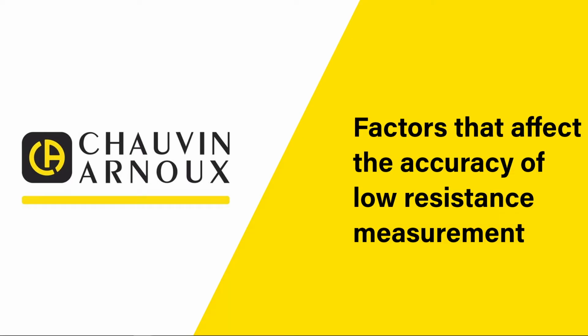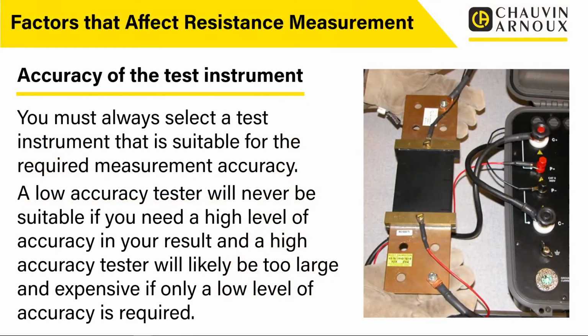So now we're going to take a look at the factors that affect the accuracy of low resistance measurement. The first factor we're going to have a look at is the actual accuracy of the test instrument itself. You must always select a test instrument that is suitable for the required measurement accuracy. A low accuracy tester will never be suitable if you need a high level of accuracy in your results, and a high accuracy tester will likely be too large and expensive if only a low level of accuracy is required. So it may sound like common sense, but sometimes people overkill what they want.